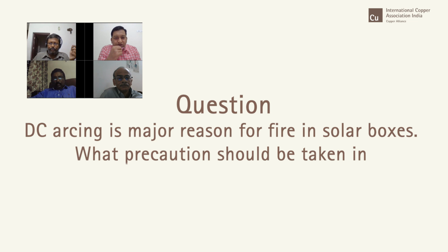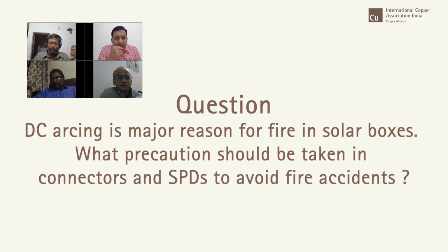Okay. Gurumurthy, next question to you from Mr. Vikas Almadi, India. Solar power is DC power. It has a voltage of 100 volt to 1500 volt DC. DC arcing is a big issue which leads to fire in solar boxes. What precautions shall be taken in connectors and SPDs and in general to prevent any sparking to avoid any fire hazards?